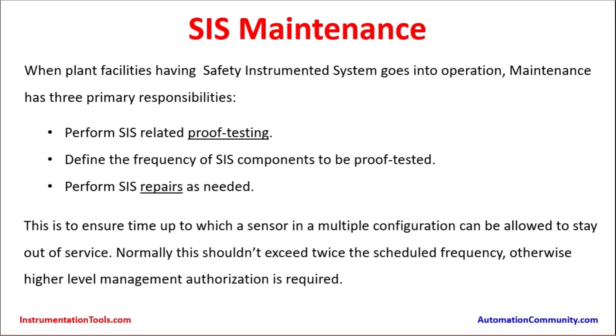When plant facilities having a Safety Instrumented System go into operation, maintenance has three primary responsibilities: perform SIS-related proof testing, define the frequency of SIS components to be proof tested, and perform SIS repairs as needed. This is to ensure the time up to which a sensor in a multiple configuration can be allowed to stay out of service.